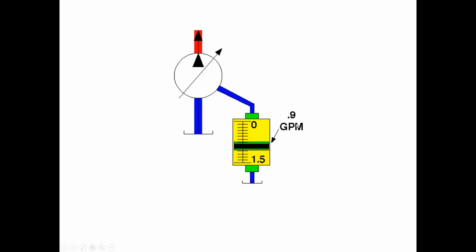Now, a real good place to put one of these flow meters is in the case drain line. We usually recommend that you install one of these in your case drain line, and once a month, write down what it says. Why does that help us? Well, as the pump wears, I shouldn't say fails yet, but as the pump wears, what happens to the tight tolerances inside there? Well, tolerances get bigger. So as the tolerances increase, what do you suppose happens to the case flow? Obviously, that's going to increase as well.